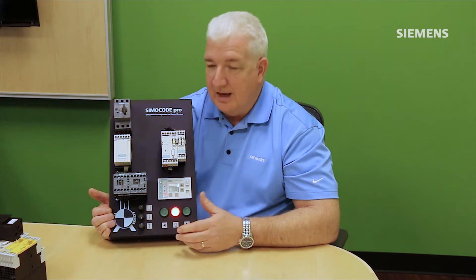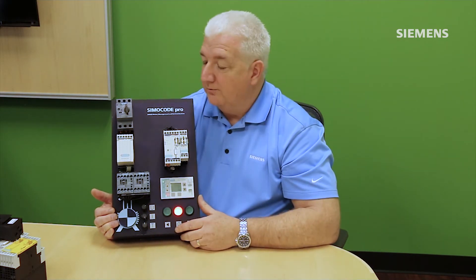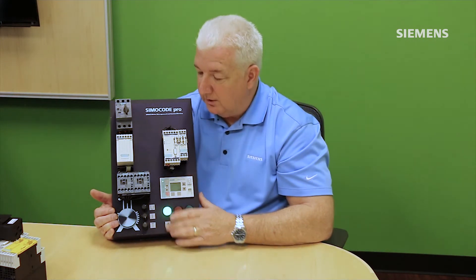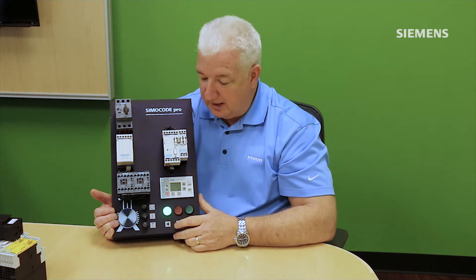SIMOCODE also performs startup verification checks. Traditionally, feedback for a proper start comes from an auxiliary contact on the contactor, but that's not very accurate — if you've lost three-phase supply, the contactor may still pull in but the motor won't spin. SIMOCODE marries the contactor-close signal with confirmation that current is actually flowing through the CT. When there's a proper starting sequence with both conditions met, SIMOCODE confirms a good start.